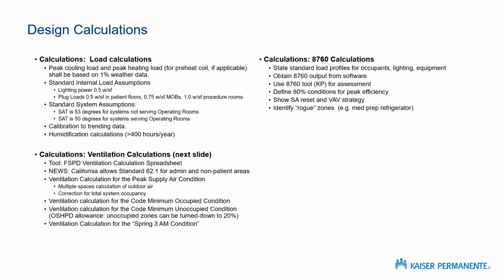again, you can calibrate your load calculations to the trend data, to the actual data, and that helps key your load calculations to reality. If you have some supply temperature trends and some valve position trends, for example, that helps to get a gut check on the numbers that you're coming up with.